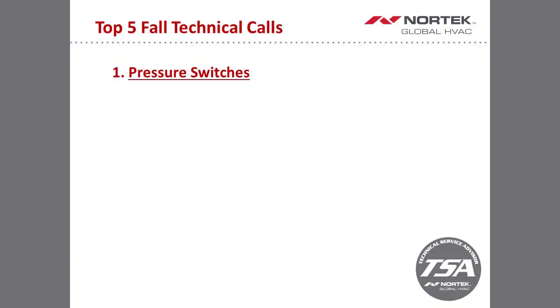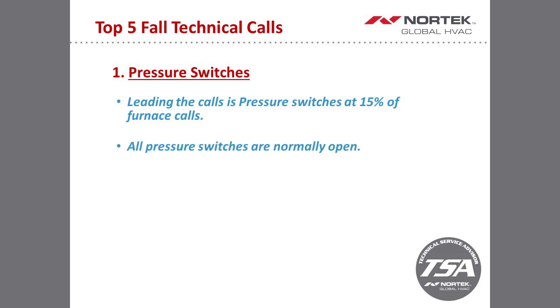The next thing we'll take a look at is pressure switch troubleshooting. By far the most common troubleshooting call we get in tech in the wintertime is pressure switch calls. This could be open pressure switch calls or closed pressure switch calls. Most of the time they're open pressure switch calls, because all of our pressure switches are normally open. That means that when the inducer kicks on, the pressure switch has to pull in in order for the furnace to light. Just keep in mind, all of our pressure switches on all of our furnaces are normally open and they have to pull in.